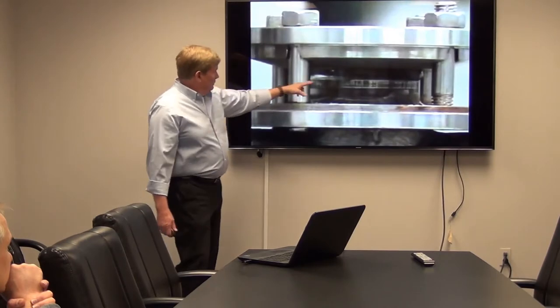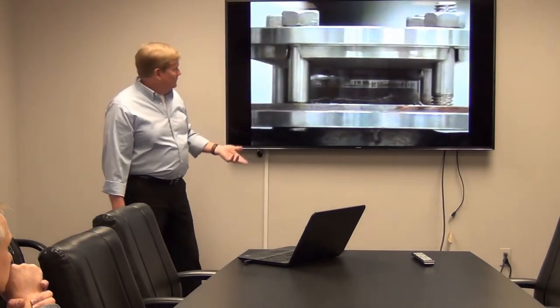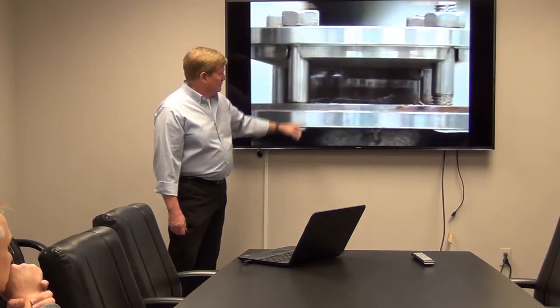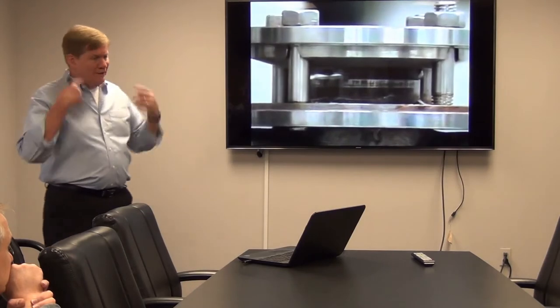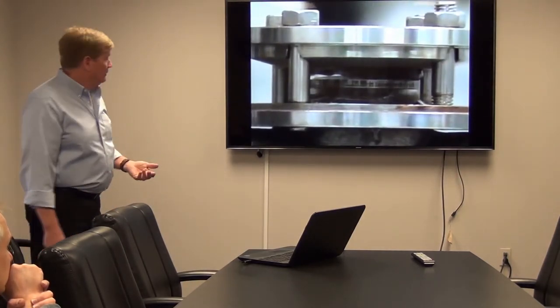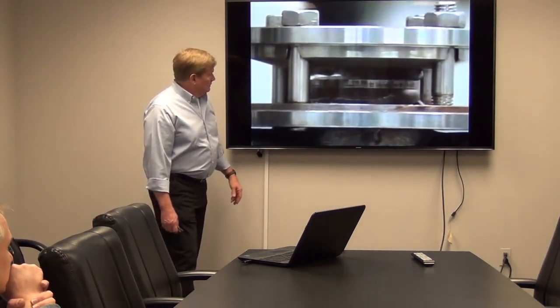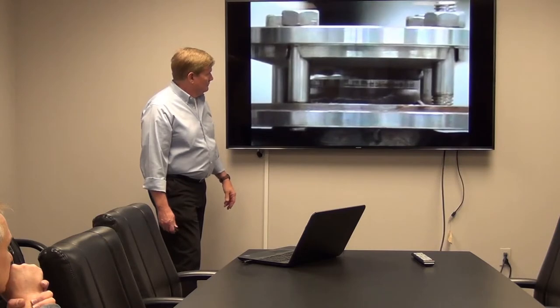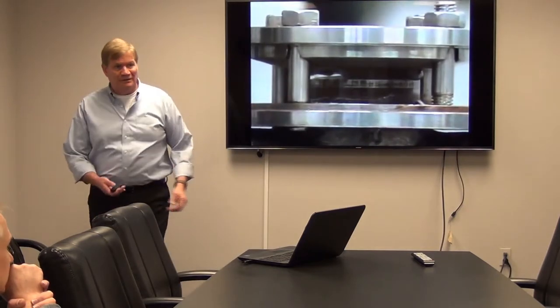So right now it's closed. So if you had the headset on, you'd be like, okay, what's it doing? That's about it. It's on and off. And when you have the headset on there, it's very audible. And that's really all you're listening for. It's an on-off trap. Easiest trap to test.